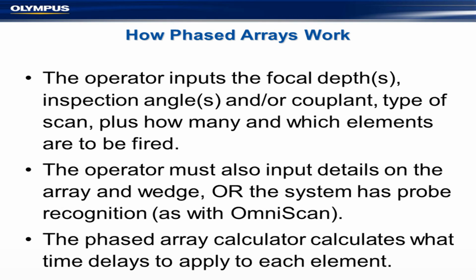Then we have a little computer inside the instrument that's called a phased array calculator, and it calculates what time delays to apply to each of the many elements. And typically, if you're firing 16 elements, it will give you the time delay for all the different elements and all the other parameters that you want to know. You, as an operator, do not have to do very much.